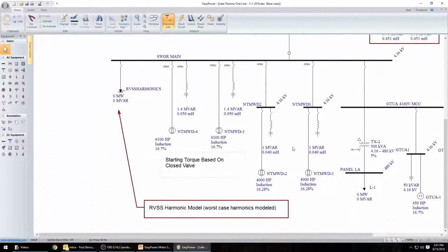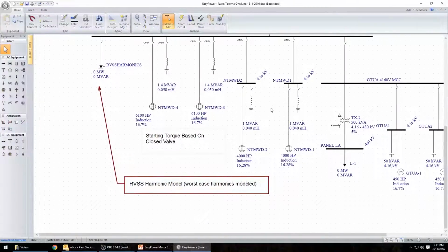In addition to that, there's also capacitors located on the terminals of the 6100 horsepower motors for the same purpose, for power factor correction. So a total of 4 pumps at this pump station, two 6100 horsepower pumps, two 4,000 horsepower pumps. All of these are equipped with reduced voltage soft starts. So for that reason, we have a model over here that represents the worst case soft start harmonics.